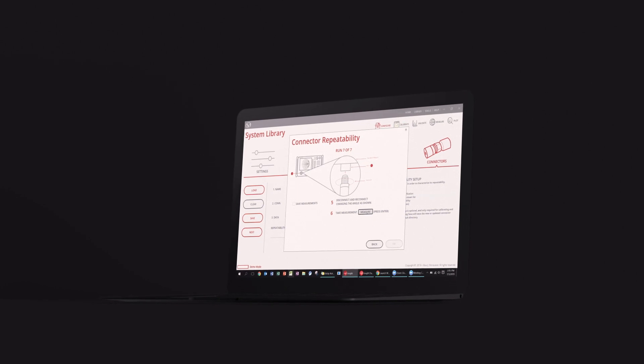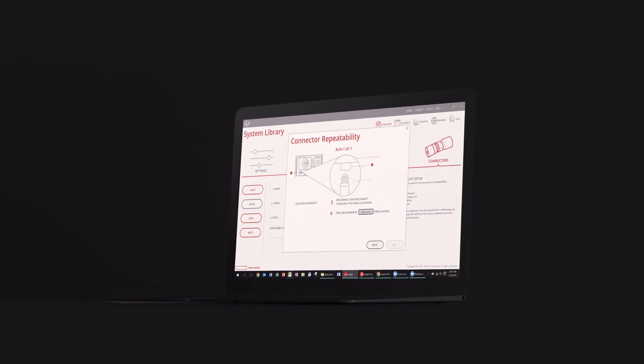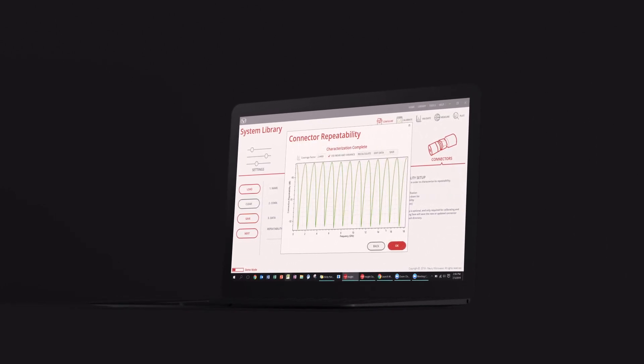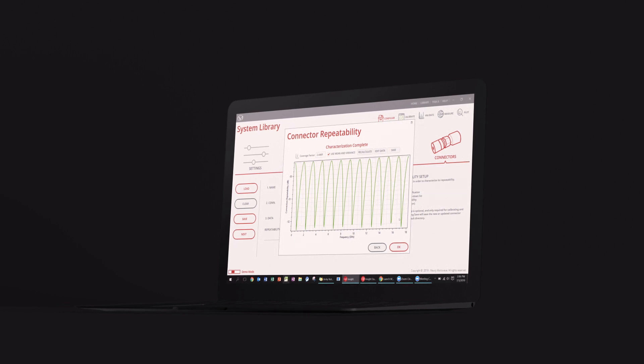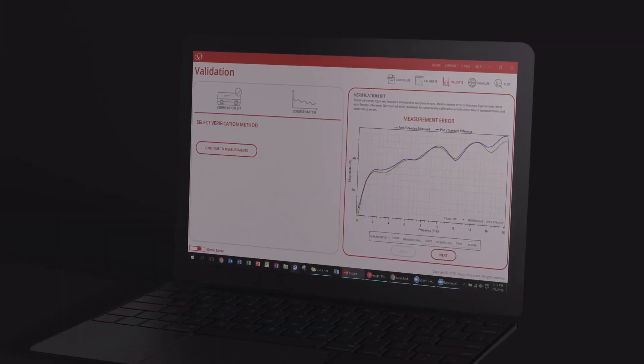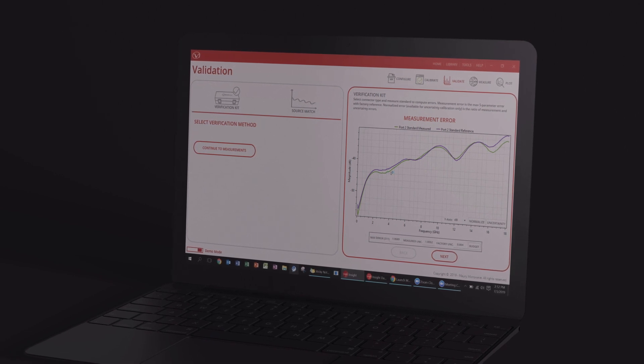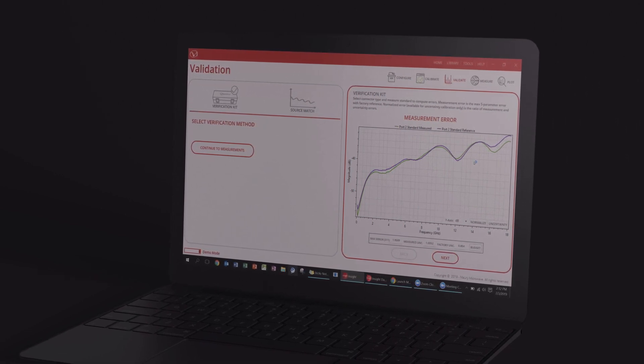The final connection interface at the calibrated device reference plane can be characterized for uncertainty by connecting and measuring a short circuit termination, then disconnecting and rotating the short circuit by 45 degrees and remeasuring, repeating the process N times. This will characterize the measurement repeatability, capturing any issues caused by connector pin depth and concentricity, as well as user errors caused by poor connector etiquette.